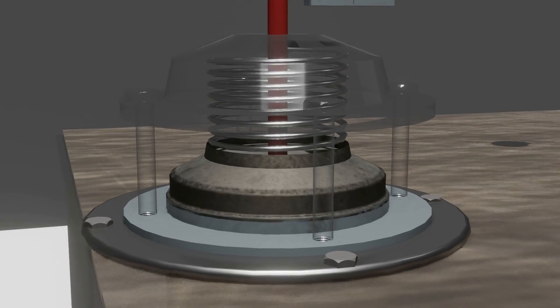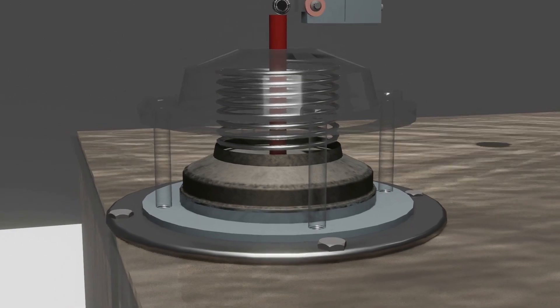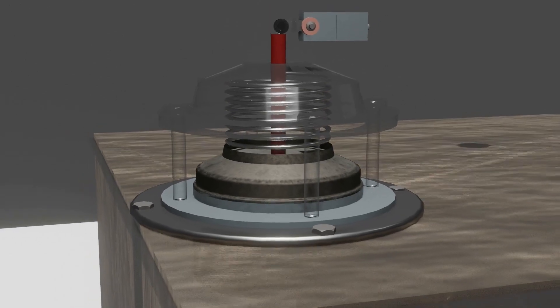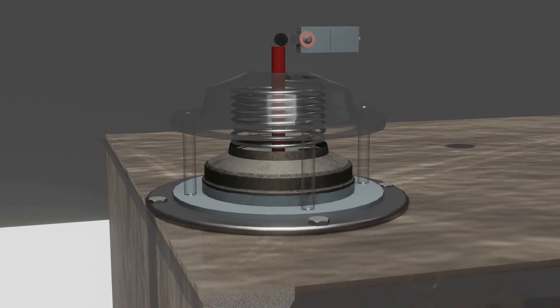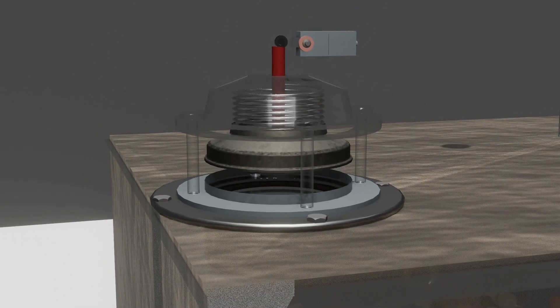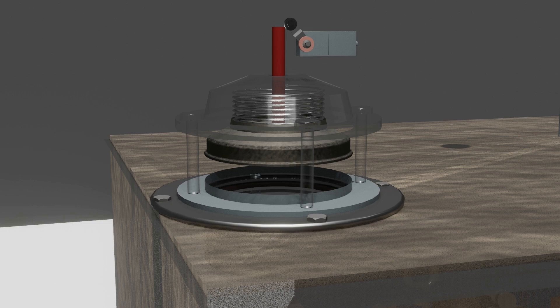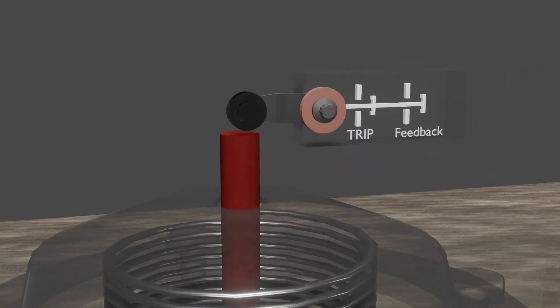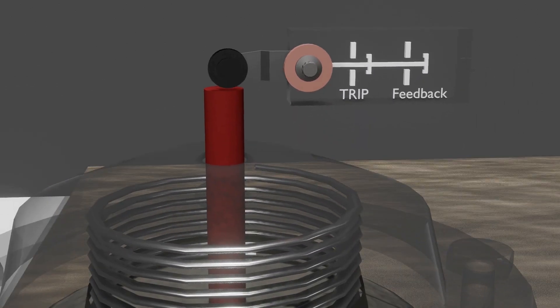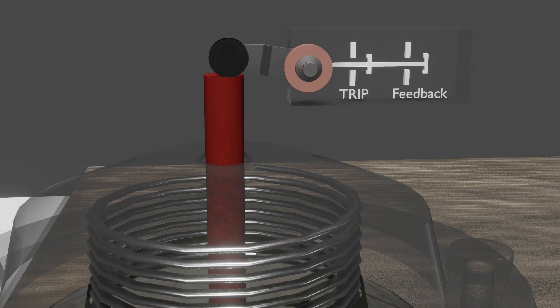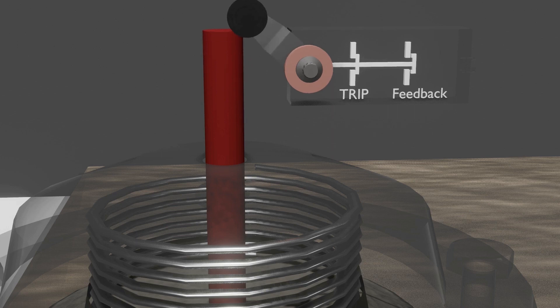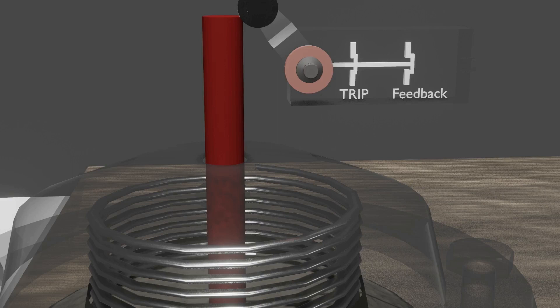Now suppose this PRV got operate. And due to that, this flag got moved like this and it will operate limit switch. So as limit switch got operate then the contact inside the switch also got changed as you see here. So it will trip the transformer and disconnect it from the upstream and downstream. And this is how PRV works on transformer.